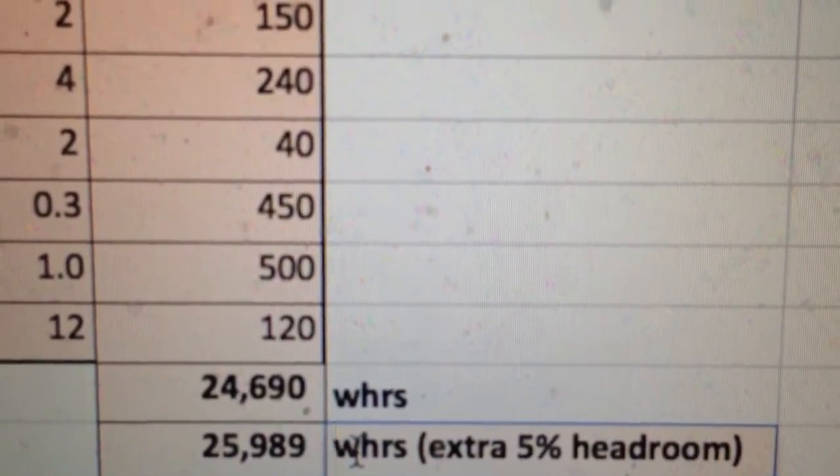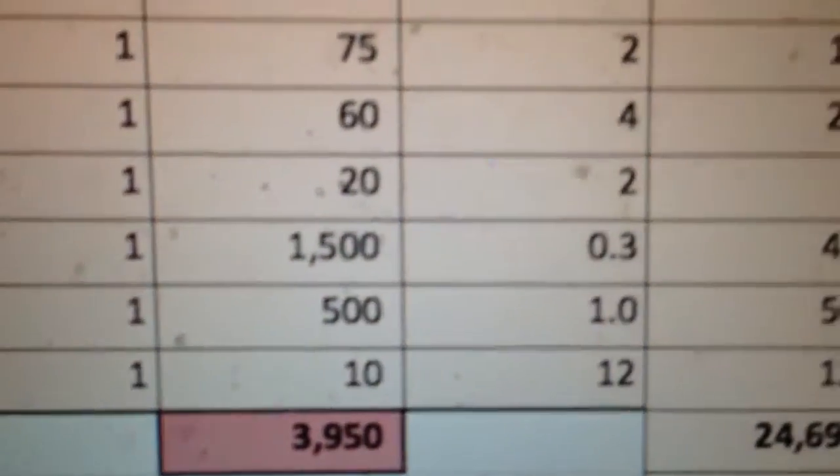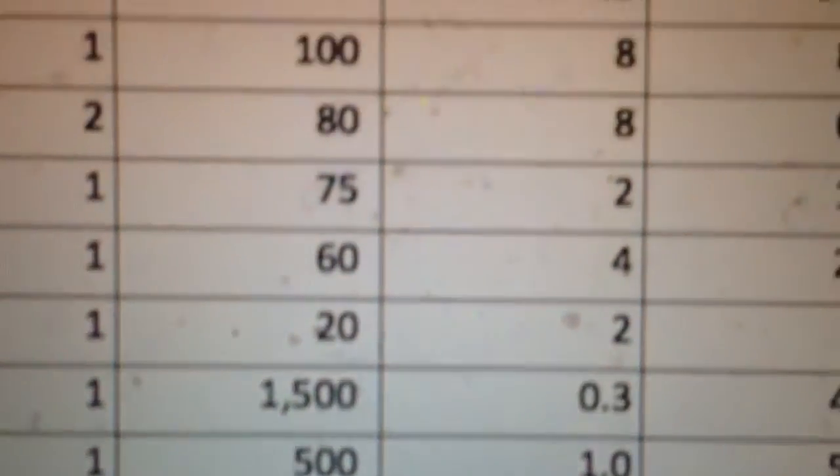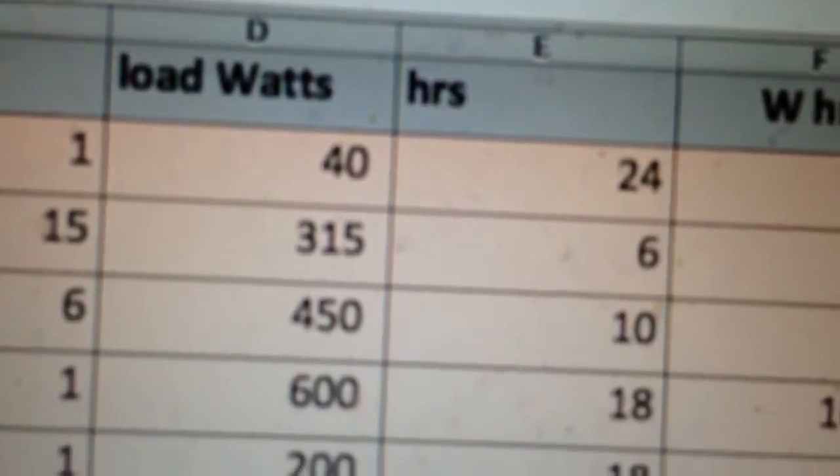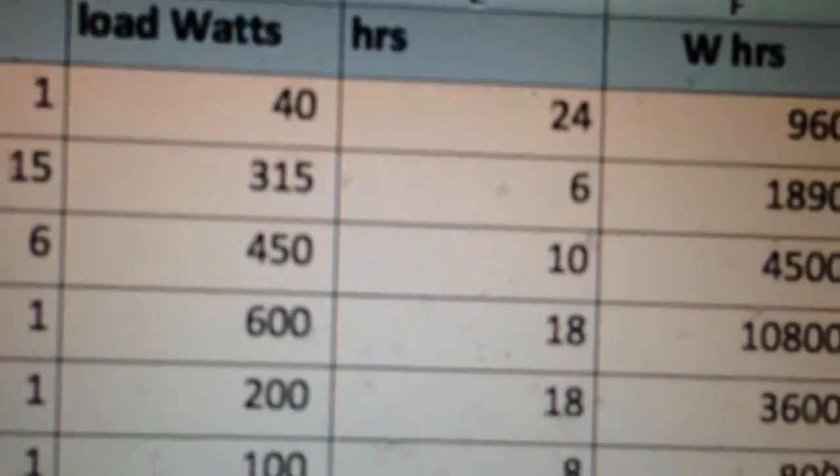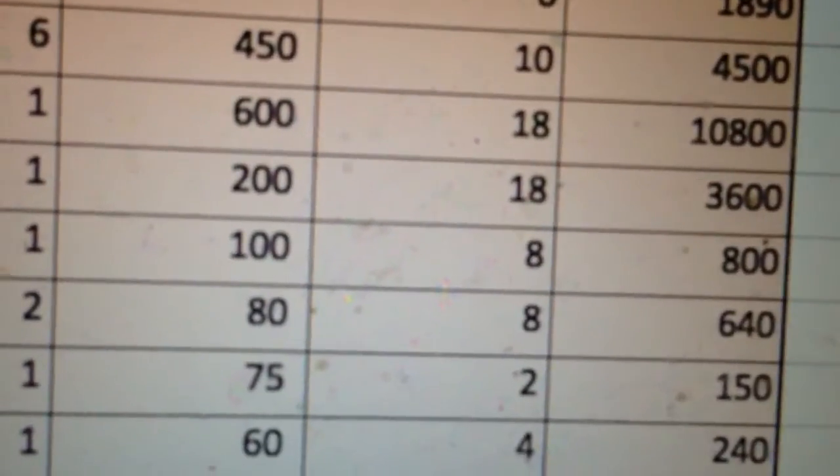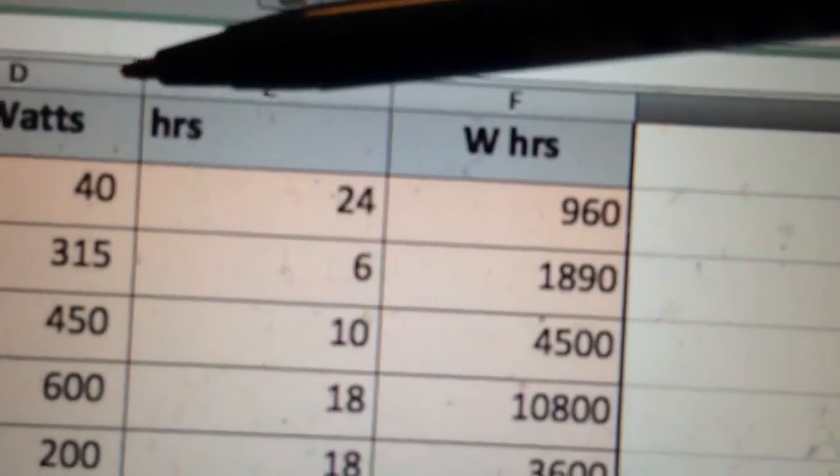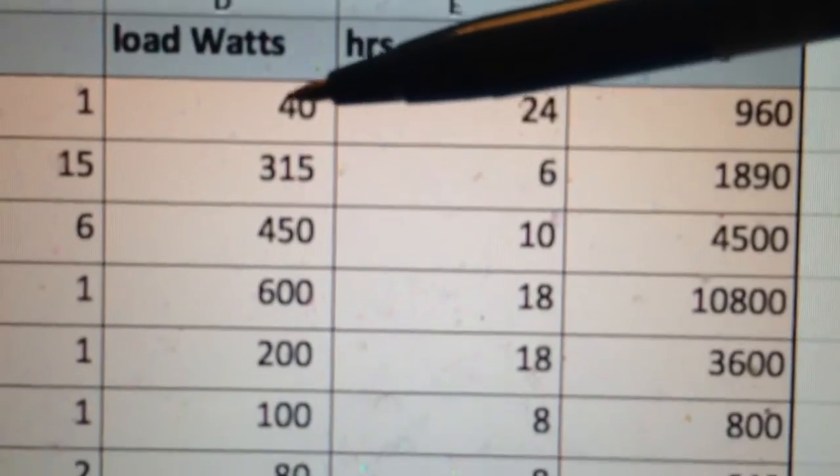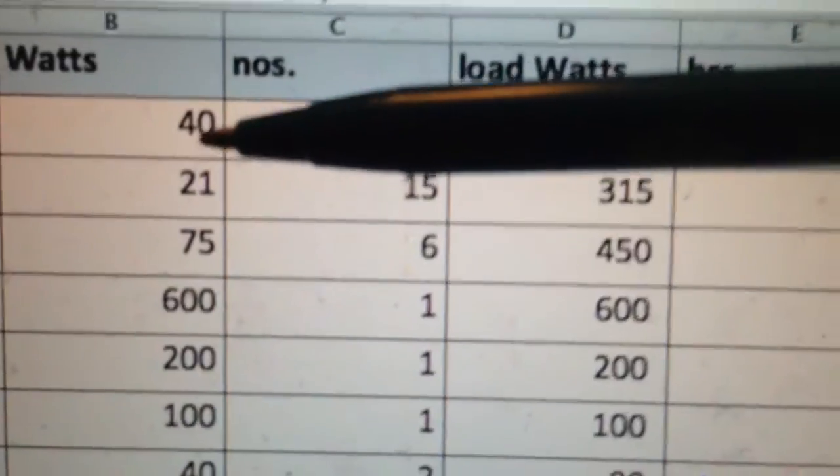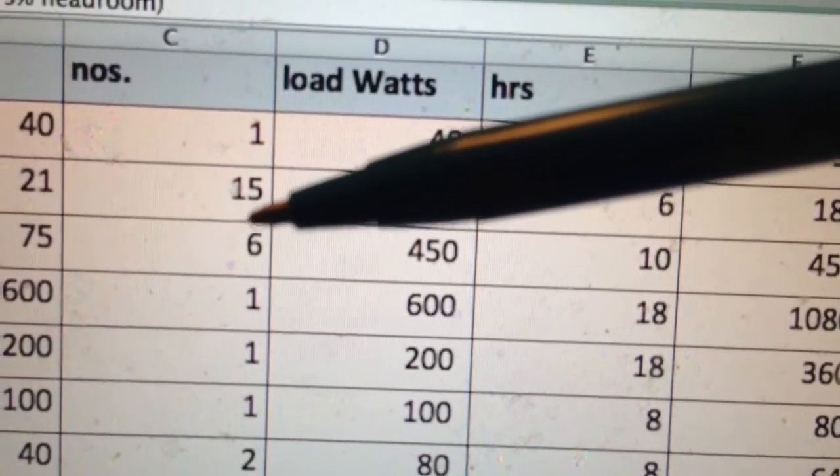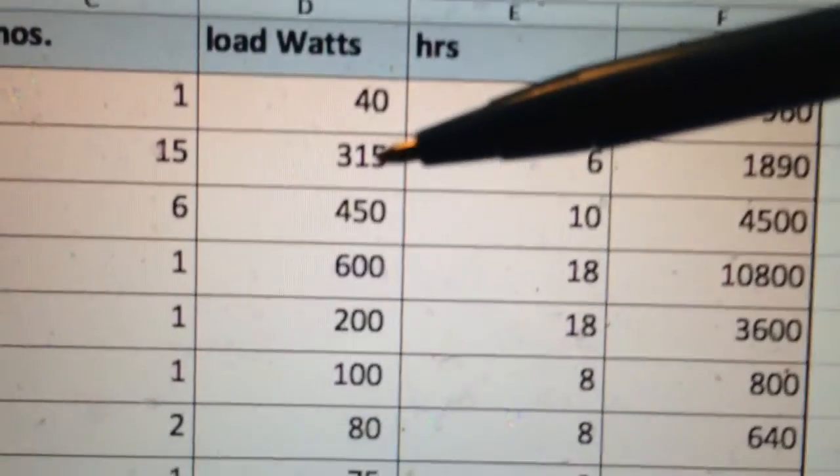Right, so there is a figure on this side here that I just want to bring your attention to. We're not going to talk about today. This is a sum of all the load, assuming every appliance you had was effectively on at the same time. So you have your watts and the number, and there you have it. For example, light bulbs, 21 watts each, 15 of them will give us a load of 315 watts in any given instant.